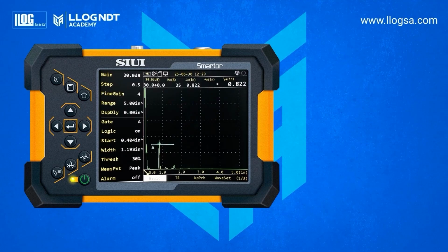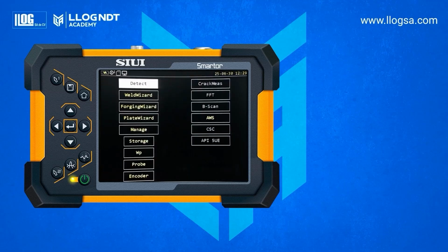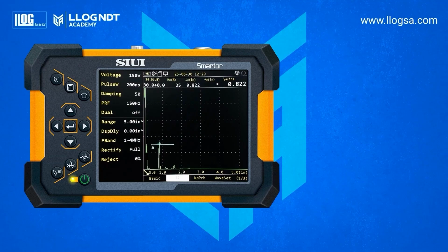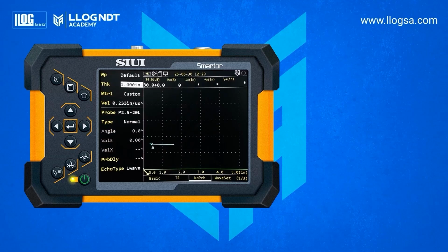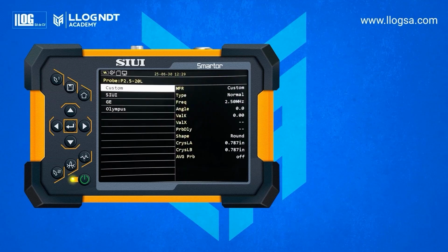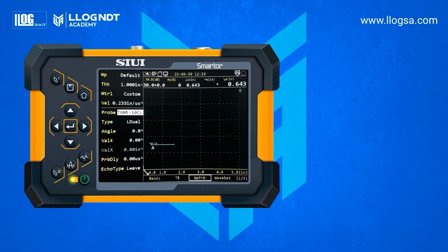Now we will perform the calibration using a dual-element transducer. We will use the same configuration previously used with straight beam. Activate the dual mode in the Transmit-Receive submenu. Set the filter to 5 MHz. Select the transducer model, which in this example is the TGM5-10CL, with a frequency of 5 MHz and a 10 mm diameter.